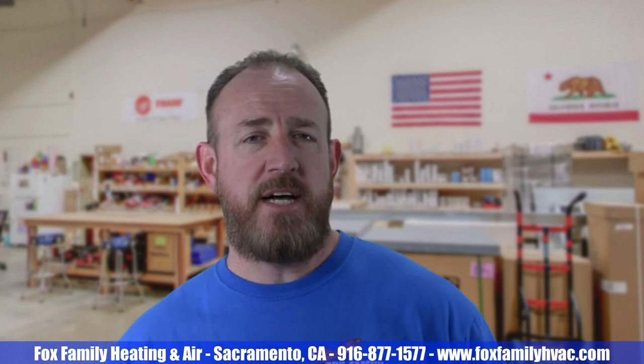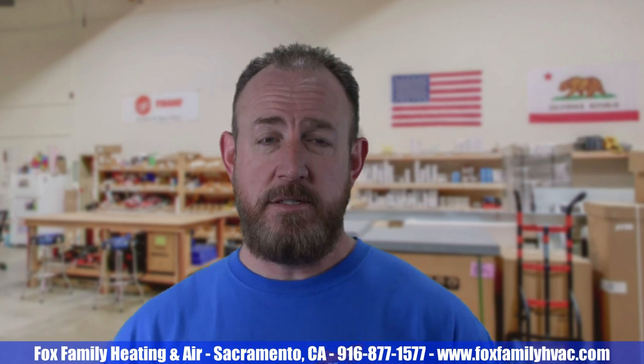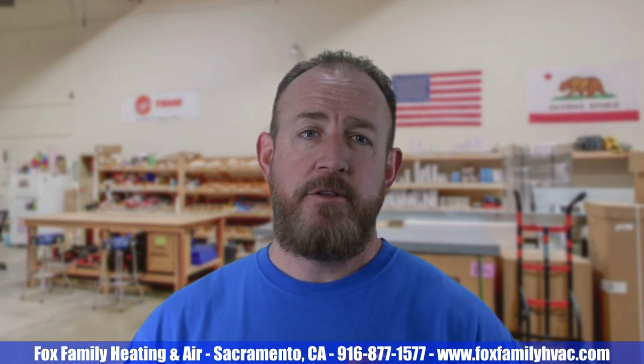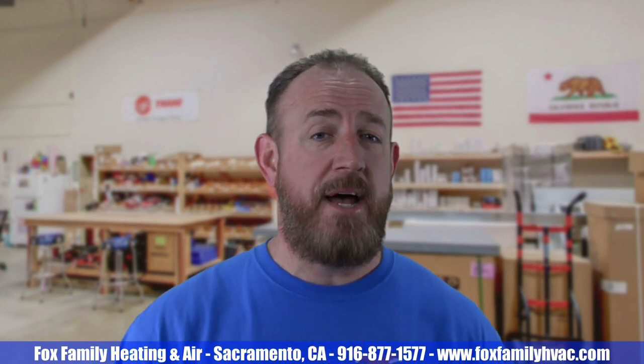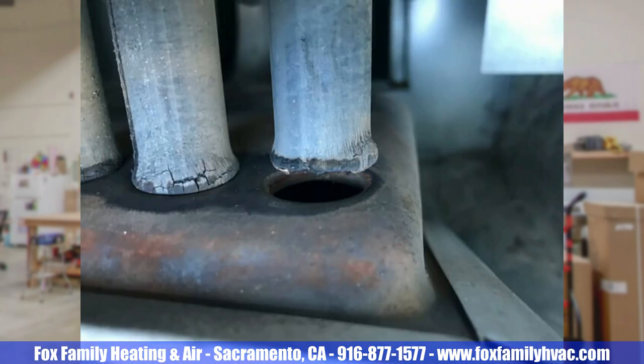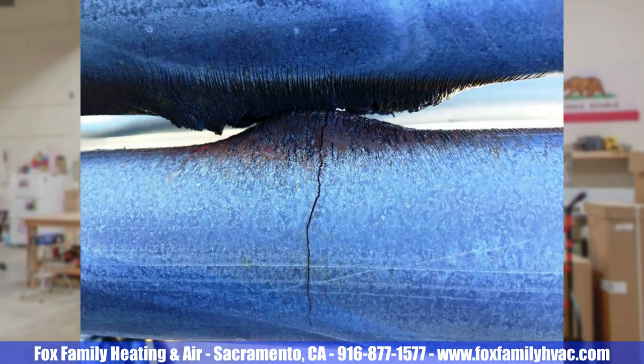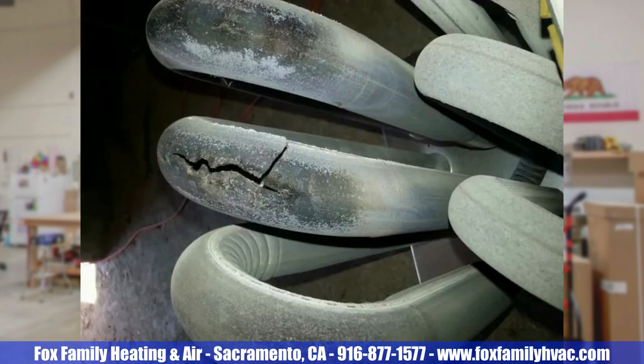Tubular designs are newer and, in my opinion, superior to clamshells and serpentines — many others will agree. They are usually made with stainless steel and bent into form at the factory. The ends of those tubes are stamped into the collector box and faceplate of the burner compartment, and it's at that connection where some tubular designs fail. Corrosion plays a big part in tubular heat exchangers failing. Eventually, the moisture, condensation, chemicals, and gases we discussed earlier can infiltrate these tubes and cause them to fail. And 90% of the time, those failures happen at the back of the tubes on the first bend.